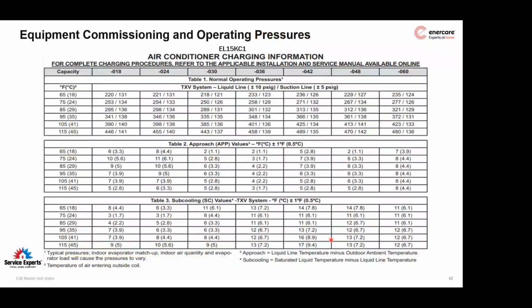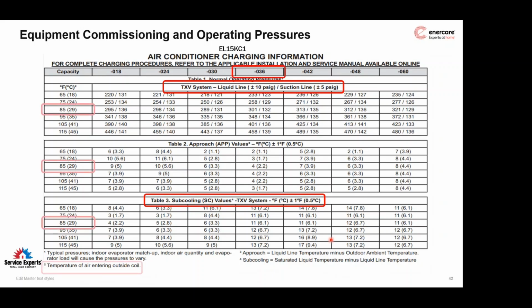One last kind of chart that's for setup and commissioning is one Lennox offers on the inside panel of the outdoor units or within the manual for the air conditioner or heat pump. So in our scenario, let's assume we've got a 3-ton unit on an 85-degree day. You have some typical operating pressures: 301 for your high side pressure, 132 plus or minus 5 psi or 10 psig, depending on what you're reading.